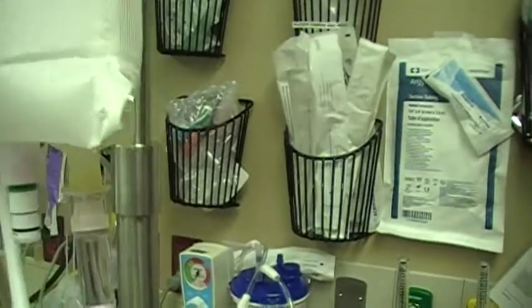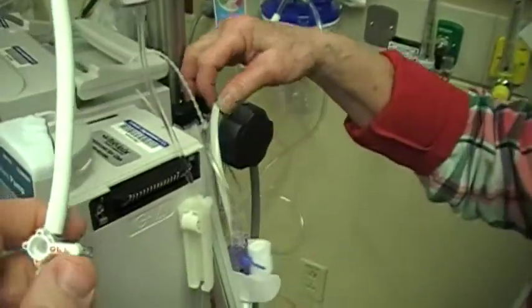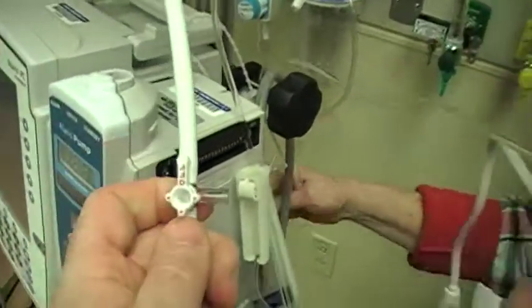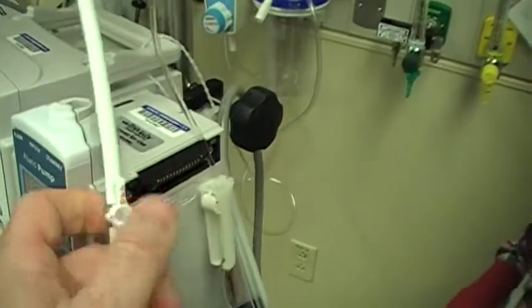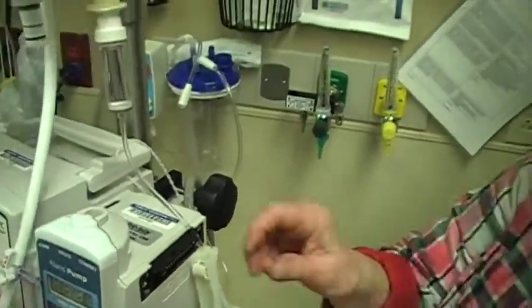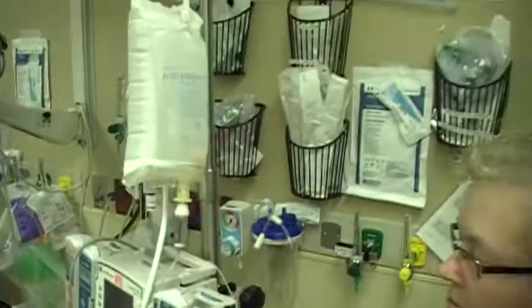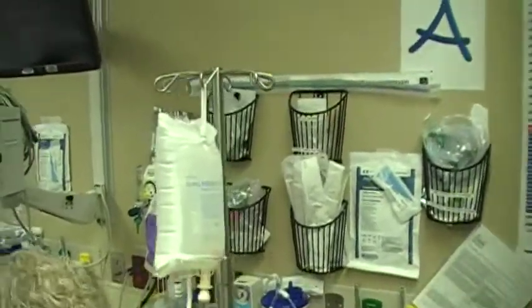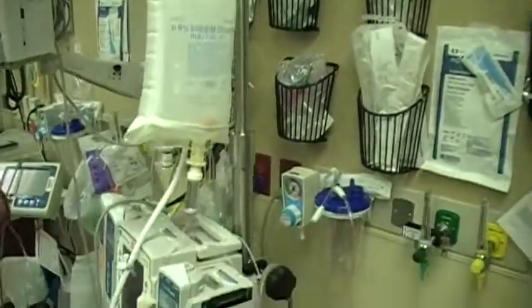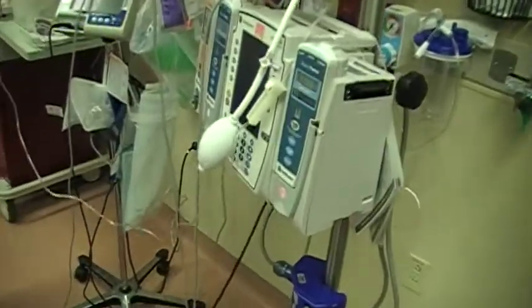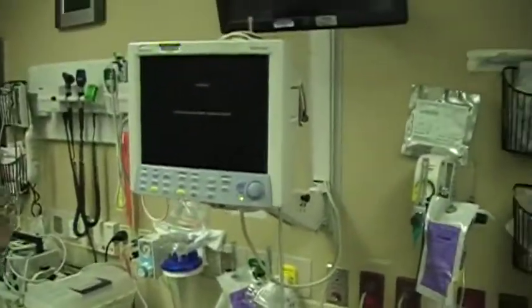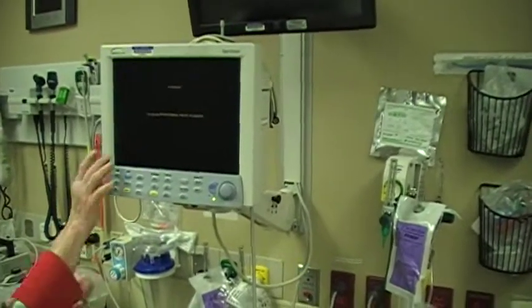Okay, once you get it up to that point, you are going to turn your stopcock off to the pressure bag, because if you don't, it will just continually slowly leak air out. At this point, we have our tubing that is hooked to the pressure bag, that is completely primed, clear of air, so we're going to move over to the monitor. First thing she's going to do is take the monitor off of standby.